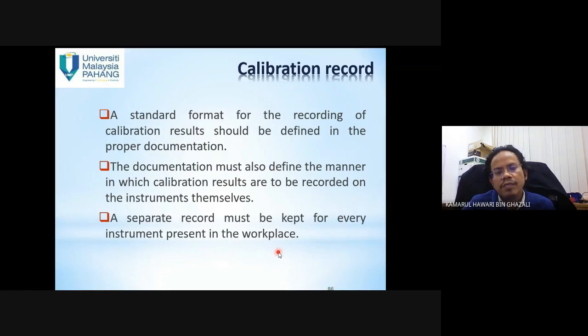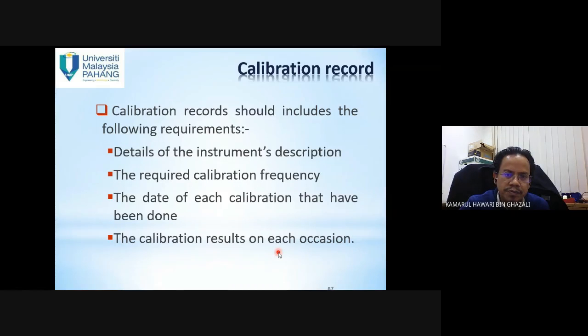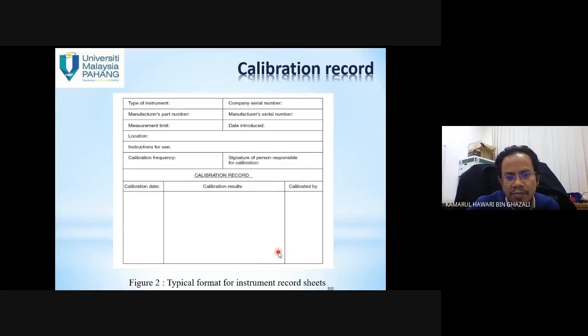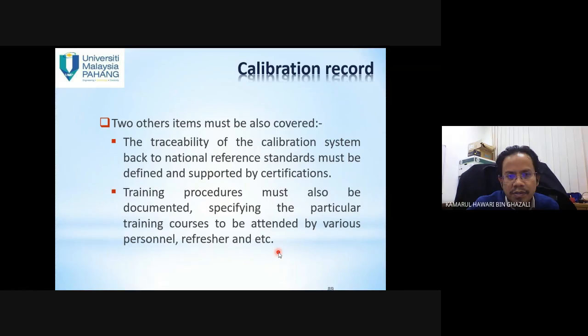Standard format for the recording of calibration results should be defined in proper paper documentation. The documentation must also define the manner in which calibration results are to be recorded on the instruments themselves. A separate record must be kept for every instrument present in the workplace. Calibration records should include the following: details of the instrument, the required calibration frequency, so how many times the instrument needs to be calibrated, the date of each calibration that has been done, and the calibration results on each occasion. This is an example. Two other items must also be covered: the traceability, and training procedures, which must also be documented, specifying the particular training course to be attended by various personnel, refresher courses, etc.